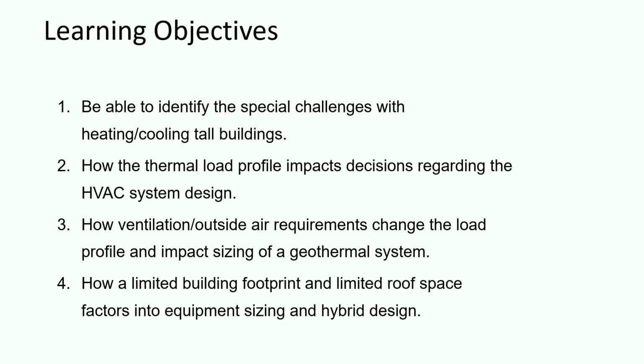But obviously there are some specific challenges with tall buildings related to geothermal, and just in general, when you start to get over around 30 stories, things tend to change between stack effects and piping pressure. And of course generally you're in a very small footprint related to the square footage of the building. So if you're going to look at geothermal and other technologies, how does that play into the land area, how much available area you have for geothermal underneath the building, and what other assets you might have for thermal resources. So we're going to look at all that.